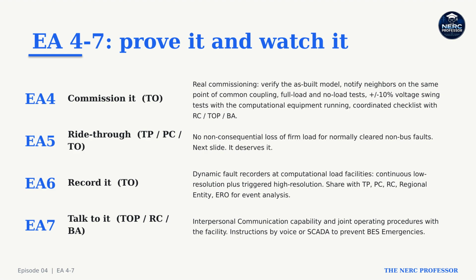Actions 4 through 7, prove it and watch it. Action 4, commissioning. Transmission owners establish a real commissioning process. Verify the as-built model. Notify neighbors on the same point of common coupling. Full load and no load testing, and where possible, a voltage swing test, 10% up and 10% down, with the computational equipment installed and running.